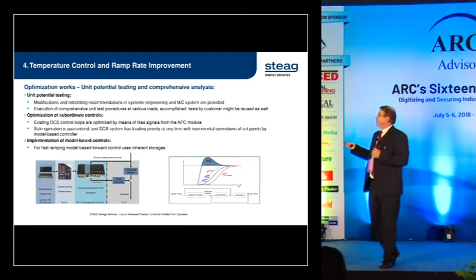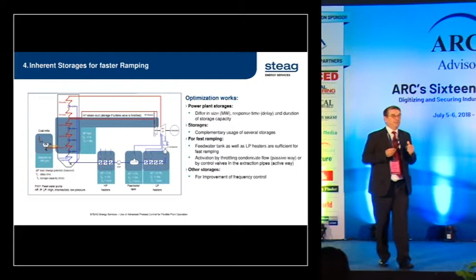The other possibility to give the fast response for the changing demand is to use the internal storage which we have in the power plant. And here are some examples of storage, already mentioned at the beginning. We can use, of course, the feed water tank. We can use the low pressure heaters, high pressure heaters. We can use, of course, the throttling of the main steam. And we can use, of course, the capacity of the mills. And every one of these storages has different features with respect to the response time, and the time for how long I can use this storage to address the problem with the changing demand.